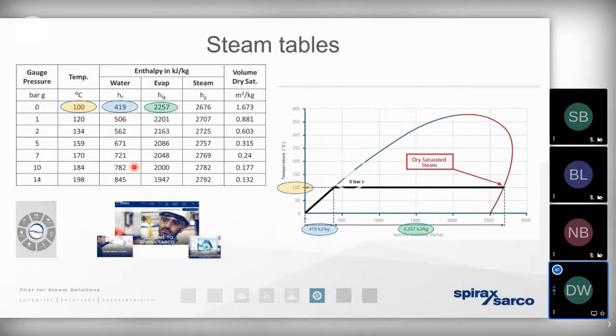So we need to put more energy into that boiling water. That's demonstrated in the next column. We can refer to that as the enthalpy of evaporation. We can also refer to it as the latent heat. So when we've added the latent heat energy to the sensible heat energy, you can see that in the next column, that's what we refer to as the total heat, the heat that is present within that mass of steam. And the final column, well, that demonstrates the volume that that mass of steam will exist at if we know the pressure.